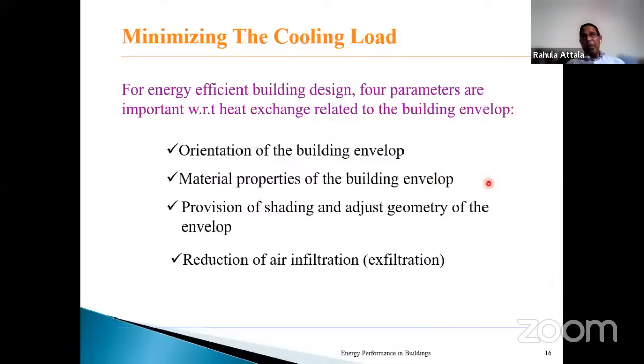Then the material property of the envelope. Why are material properties important? Because we discussed that the cooling load is affected by the storage. So material properties will decide. If it's brick, there will be one kind of storage. If it's concrete block, that will be another kind. If it's wood, something else. If it's a steel structure with some other material mixed with, let's say, bricks or anything, then another storage level. So therefore, building envelope material will have an impact on that. Provision of shading: the building envelope can be shaded from outside, and the windows can be shaded. And the other one is reduction of air leakage into the building or from the building to the outside, which is unintentional. That's why it is called air infiltration. And all this will reduce the cooling load beyond what we expect.